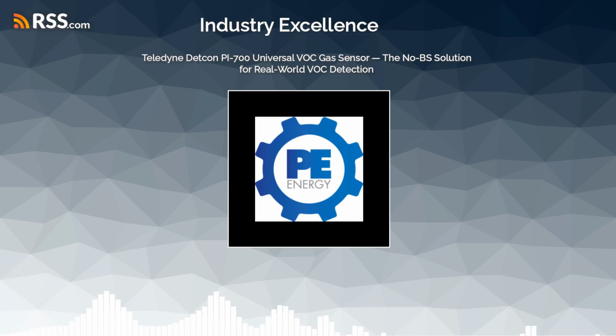And then there's the VOCs, the volatile organic compounds. They use a PID, which stands for photoionization detector. Right. Think of a PID as a broad-spectrum sniffer. It uses an ultraviolet lamp to blast the gas molecules, physically breaking them into ions so it can measure the current. And the specs call it a universal non-selective VOC sensor. That non-selective part is key. It's excellent for detecting a leak of something hazardous, even if the sensor can't always tell you exactly what that something is. It just says, hey, there's a bunch of organic vapor here, be careful.